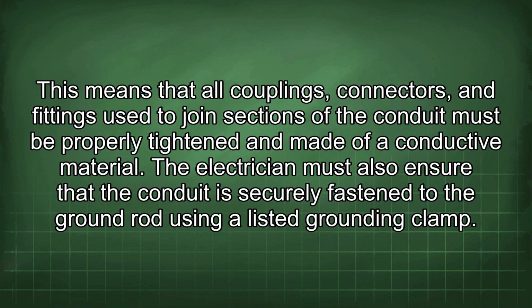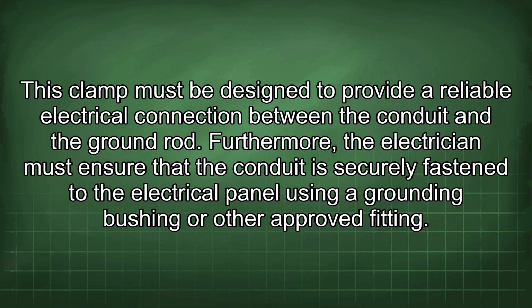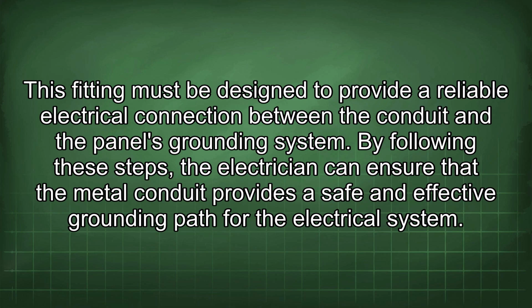This means that all couplings, connectors, and fittings used to join sections of the conduit must be properly tightened and made of a conductive material. The electrician must also ensure that the conduit is securely fastened to the ground rod using a listed grounding clamp. This clamp must be designed to provide a reliable electrical connection between the conduit and the ground rod. Furthermore, the electrician must ensure that the conduit is securely fastened to the electrical panel using a grounding bushing or other approved fitting.